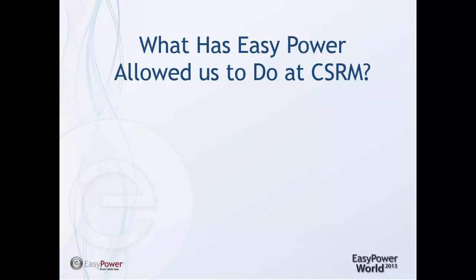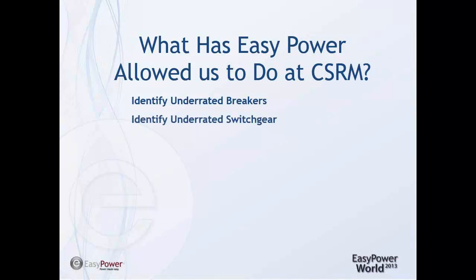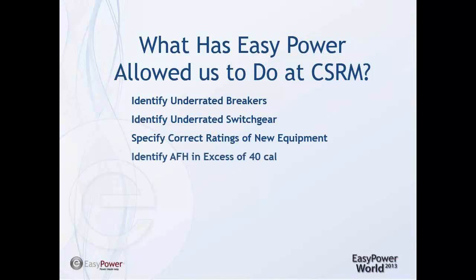What are some of the things EasyPower has allowed us to do at Cascade Steel? It's allowed us to identify underrated breakers and underrated switchgear that we have in service. When we do replace switchgear, we know exactly what parameters to specify for the new switchgear.